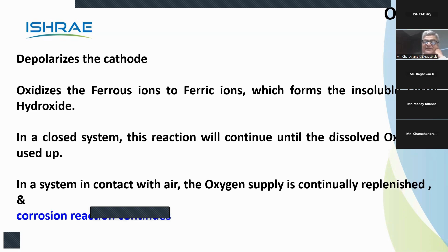In the case of boilers, we add chemicals which can literally eat up the oxygen from the water. But in cooling water or chilled water systems, we create a kind of film which will not allow the oxygen molecule to attack the bare metal. This is elaborated in the next session, so I won't spend time on it now. But these corrosion reactions are the underlying philosophies. Cooling water or chilled water is not aggressive in nature, whereas boiler water is very aggressive. These are the things normally taken into account when devising treatment philosophy.